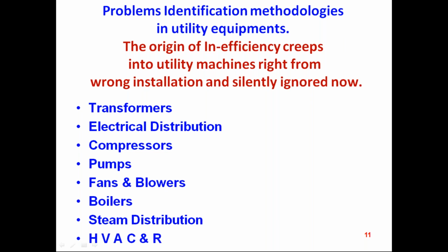Lots of changes are happening now. Thanks to IS 1180, the latest standard for transformers, it calls for operating the transformer where the copper loss and the iron loss, that is the load loss and the no-load loss, are always equal. It comes at around 35 to 40% loading for the given transformer. Before, the industry was operating transformers at almost 80% load. Now, the transformer is very healthy if it is operated in the mid-range only. See, the loading of a given machine decides the efficiency of the machine also.